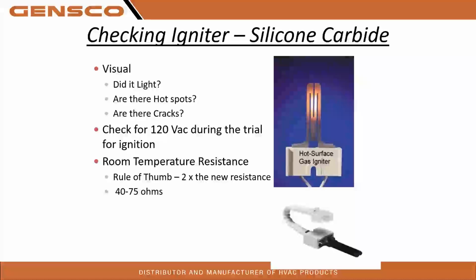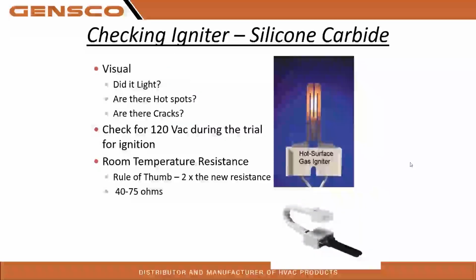So we're going to visually inspect it. Are there hot spots? Are there cracks? Is there something wrong with it? We're going to look for voltage. If it's 120 volt during the trial, we're going to look for 120 volt. 80 volts is really hard to do because that voltage peaks around. It jumps around all over the place because it has a learning routine. So really with the 80 volt igniters, we're just looking to see if they glow. And then of course, resistance at room temperature too, right? So I'll close this. So looking at it, visually inspecting it, attempting to fire with it, seeing what happens.